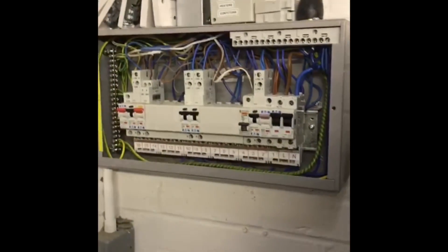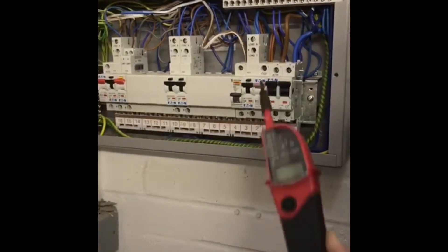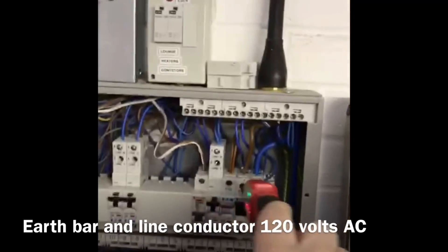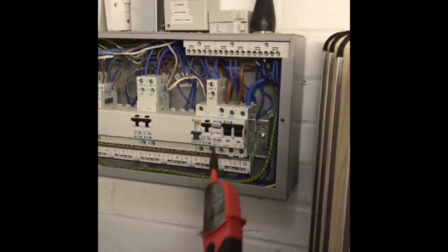We're at this distribution board. Go between the earth bar and the line conductor coming in - what's that reading? It's reading 120. Okay, and then go between the earth and the neutral.